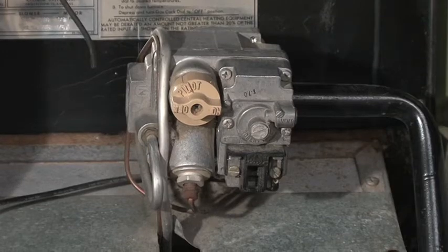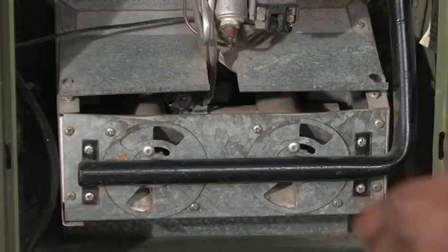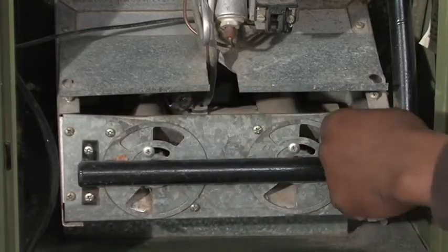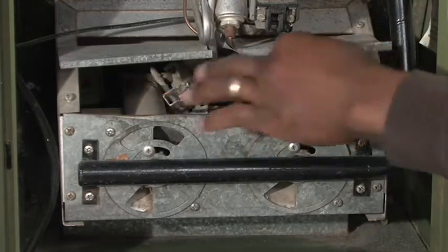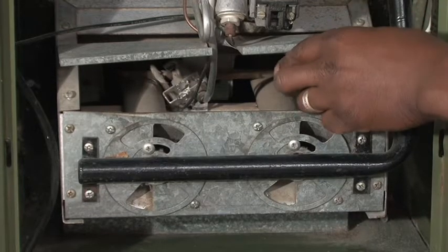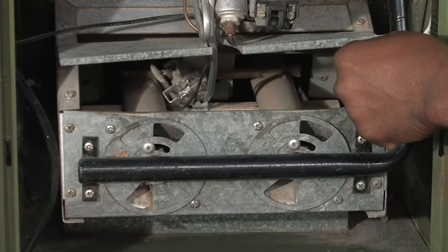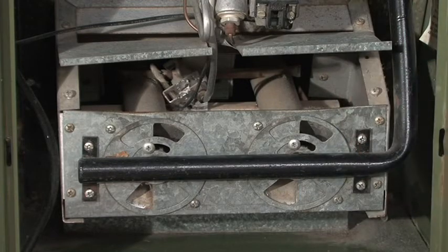Below that fan limit switch, we have our gas valve. Below the gas valve are the burners. If we look at the burners, we see that they actually go into the bottom side of the heat exchanger. So when the gas is burning, the warm combustion gases are going into the bottom of the heat exchanger, making their way up through the heat exchangers. The blower is blowing air across the heat exchangers, extracting the heat out of those combustion gases, and then they exit the heat exchanger at our draft diverter and make their way up the flue pipe.